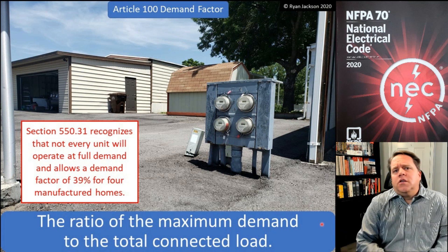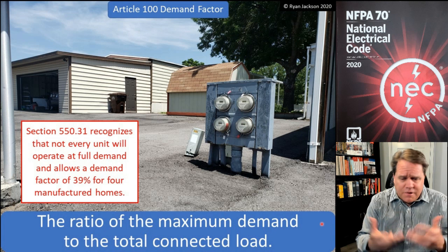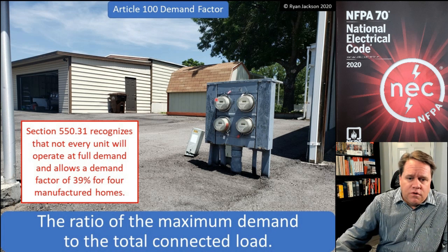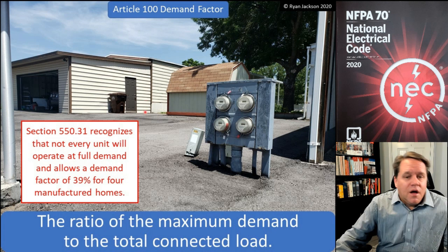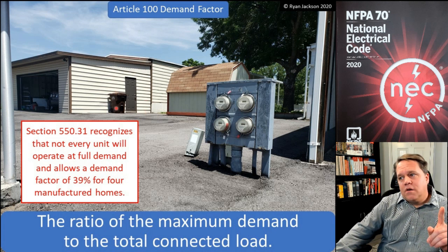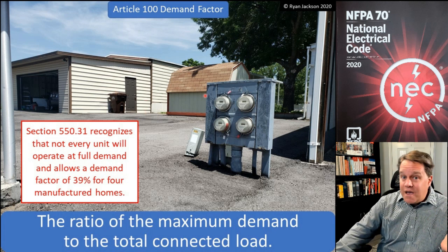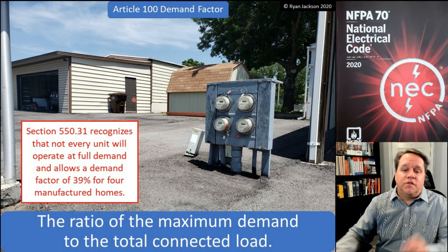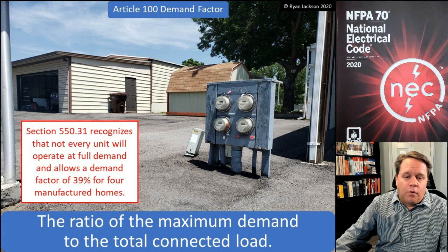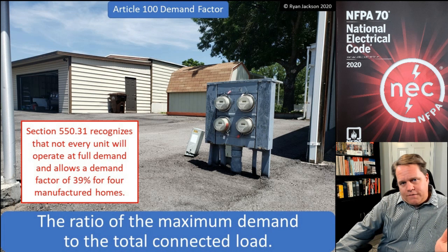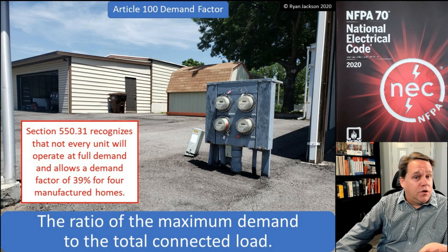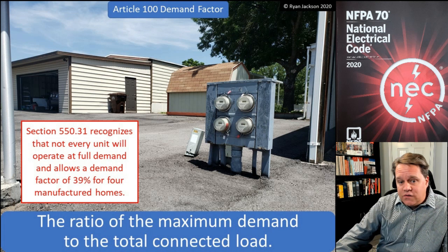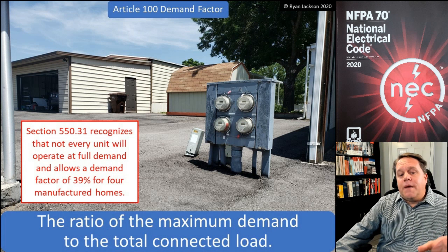You can use 310.12 to size it, but basically you have to assume we're going to be using everything in the house at the same time. We also recognize that maybe one of them is using everything all at the same time, but certainly not all four of these are — and that's where we have a demand factor. Section 550.31 recognizes that fact.